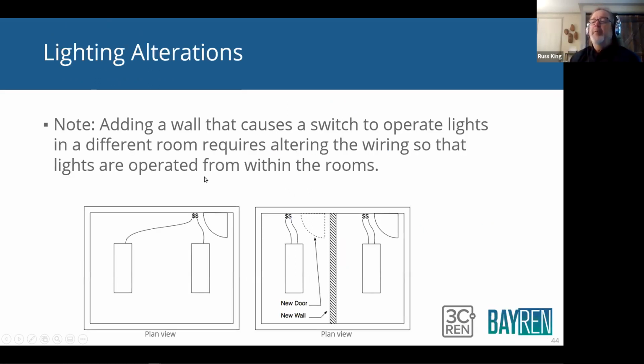Here's an example of how making a change to a space can trigger some mandatory lighting requirements when you're not actually changing the lighting. All right, let's say you've got a big office that's got two big fixtures in it, and you're going to convert that office into two spaces by building a wall down the middle and put a door here, okay? So if you were to just put a wall down the middle and put a door over here, the switch to this office would be in the other office. That's not allowed, all right? The mandatory measure says each enclosed space must have its own switch, all right? And in addition to that, it has to be dual level switching. Every enclosed space has to have the ability to turn the lights off by about half, okay?